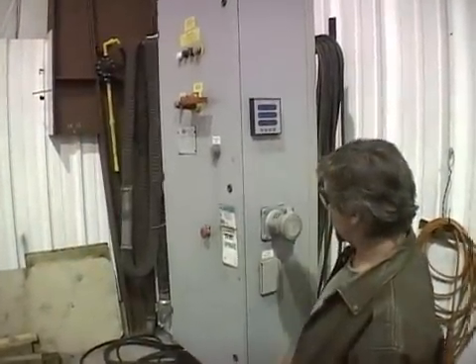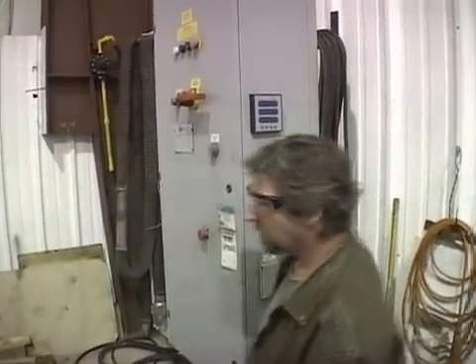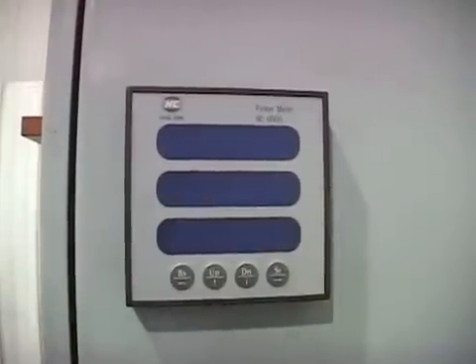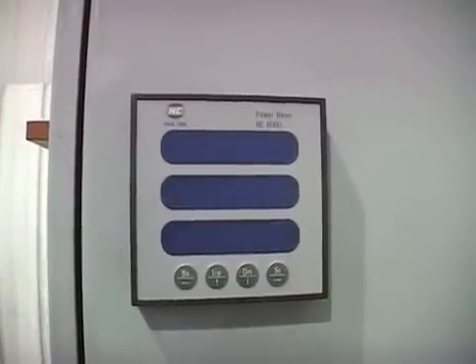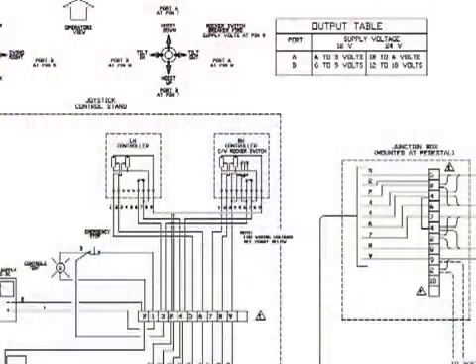Electrical testing is then performed. This includes the main electric motor and the cooler electric motor. Amperage and voltage values are documented under no load, full load, and complete nameplate data.